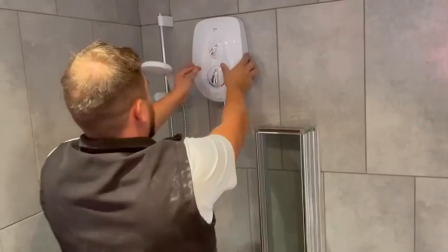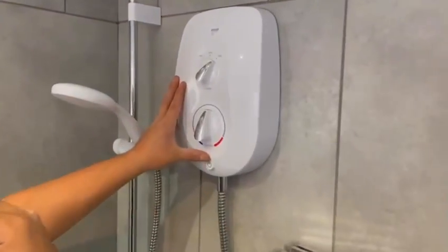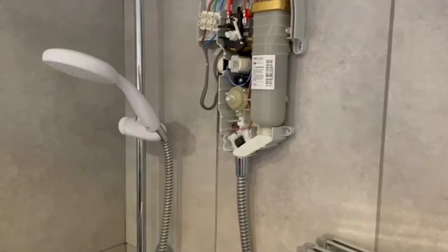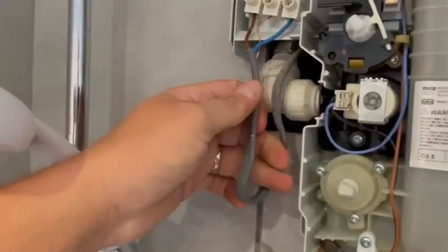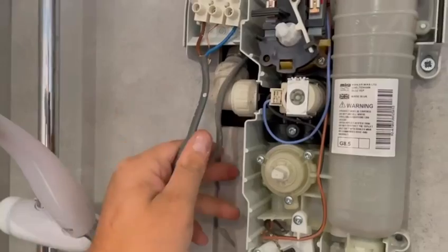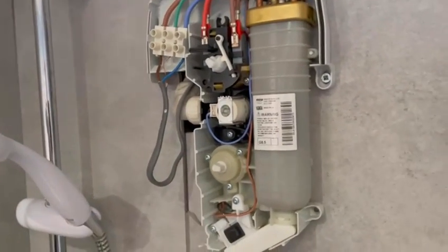One of the things they said was there was a bit of an issue with the shower. You can see it's a nice Mira electric shower — I think it's eight and a half kilowatt. And when we look at it, it's got a one and a half millimetre squared cable, and no isolator by all accounts.